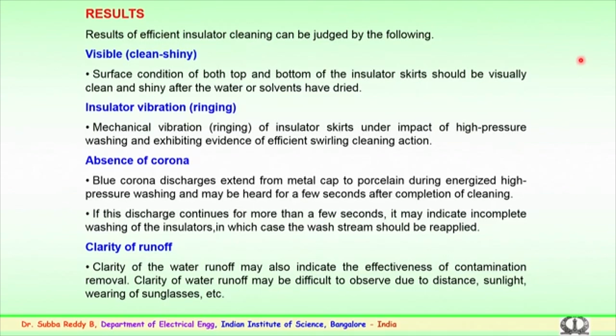If it is during the energized condition, it should be noticed that the blue corona discharges which extend from the metal cap to the porcelain during energized high-pressure washing may be heard for a few seconds after completion of the cleaning. Once the insulators are completely clean, the discharges have to be reduced. If the discharge continues for more than a few seconds, even after the insulator is completely dried, this may indicate incomplete washing of the insulators, in which case the wash stream should be reapplied. Once the cleaning with high pressure washing is done, corona activity should completely die down or disappear. If activity persists, it is an indication that the insulator requires more cleaning or a better cleaning method, so that corona activity is not there on the surface.